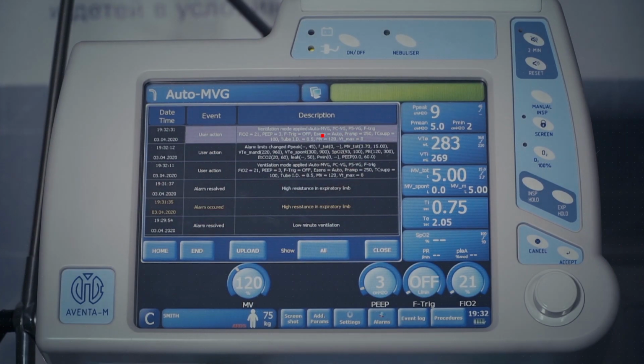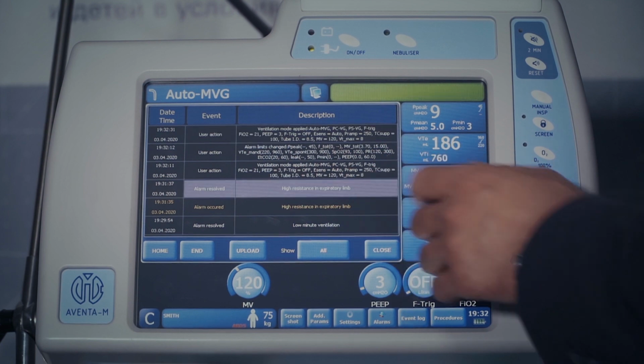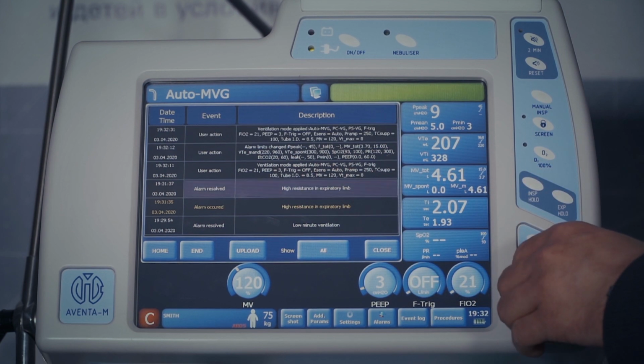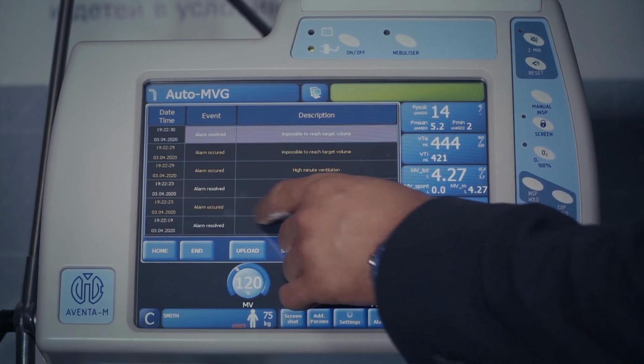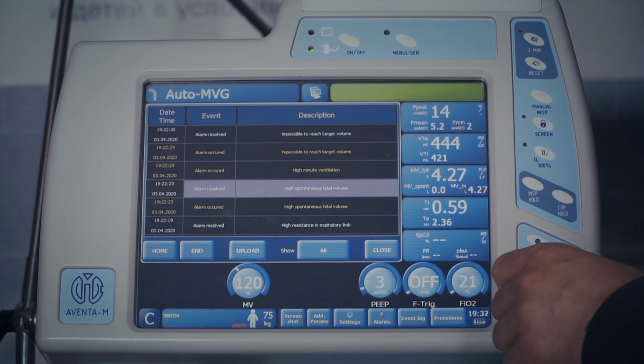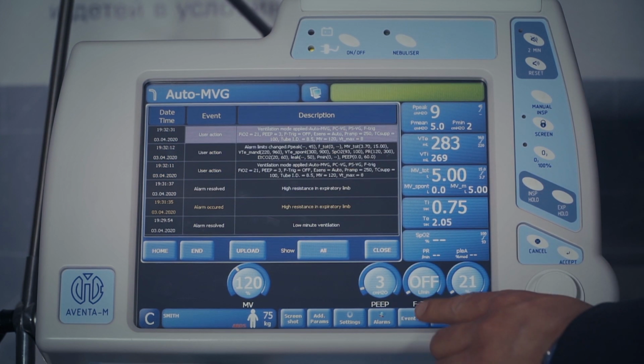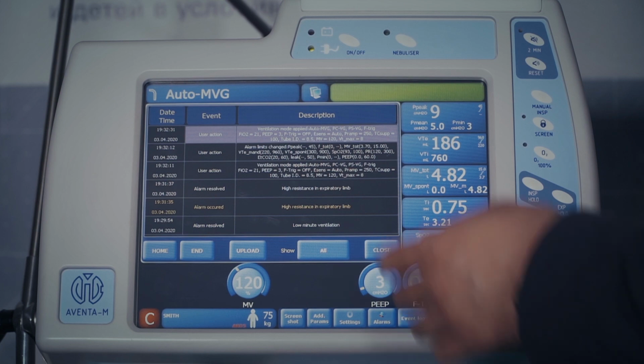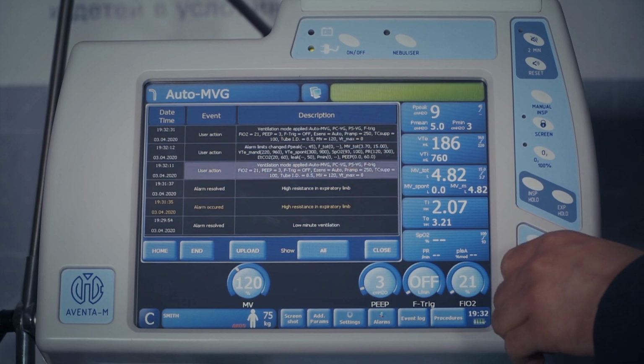Any change of lung ventilator Aventa-M settings, as well as alarm actuation and information about alarm cause elimination, are recorded and stored in the events log with a capacity of up to 5,000 events. The log can be called up by pressing button Event Log in the lower part of the screen.